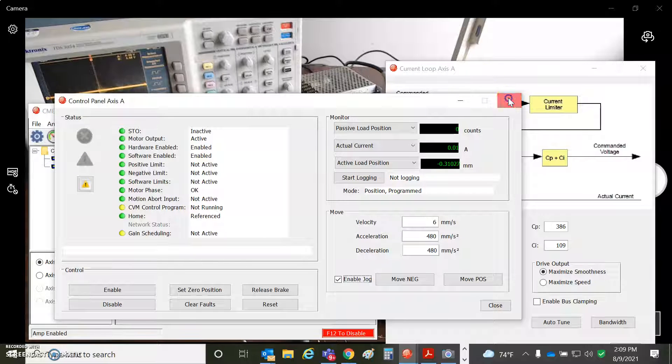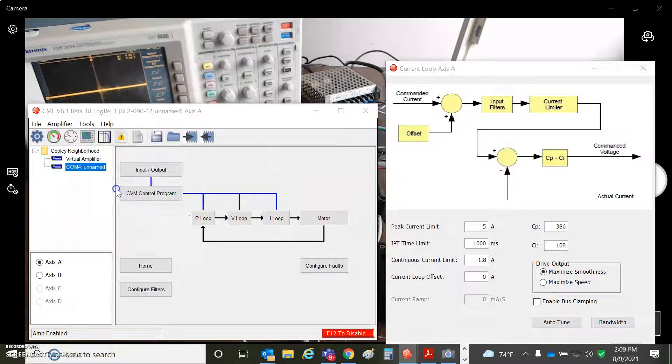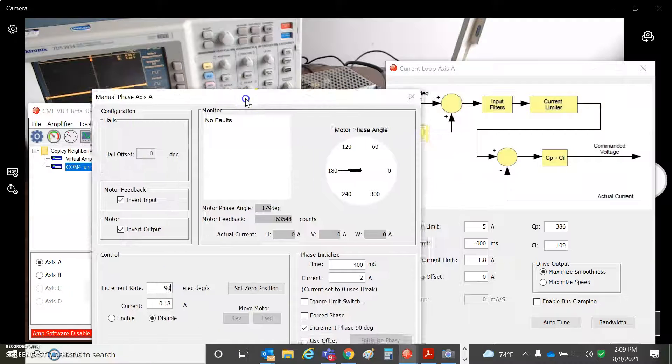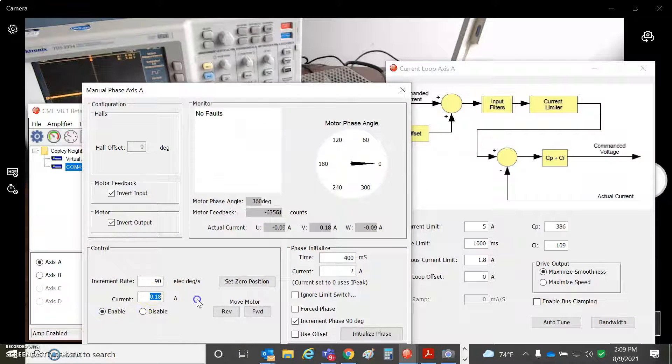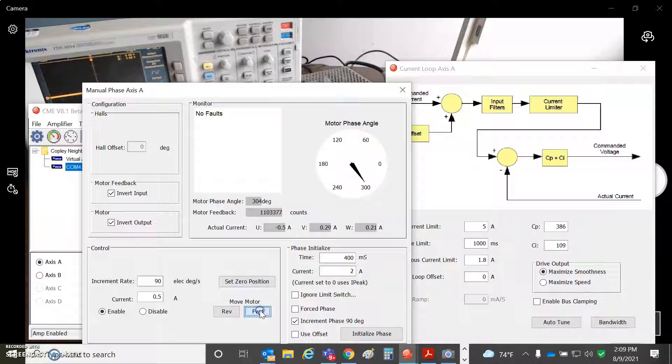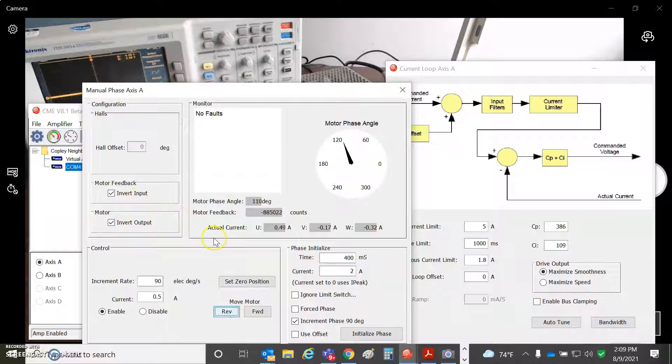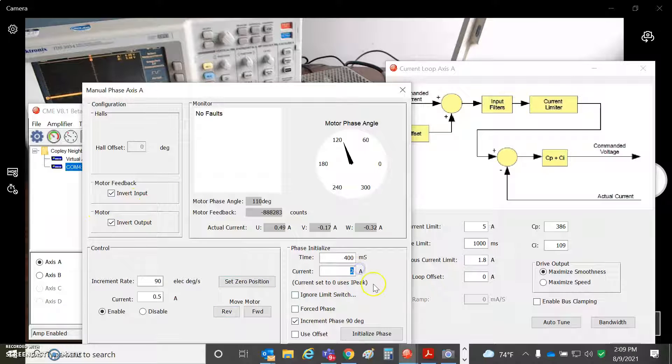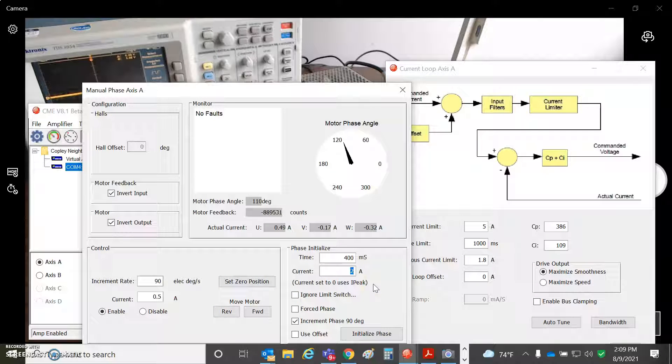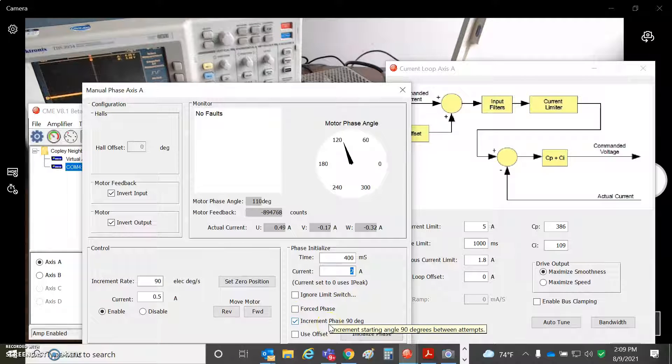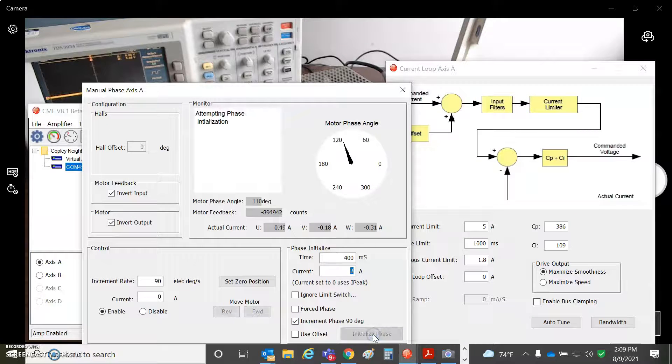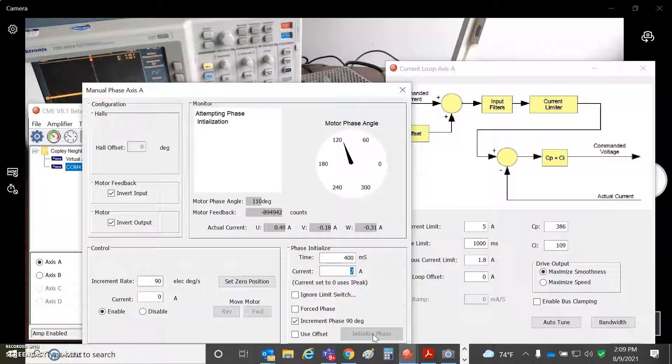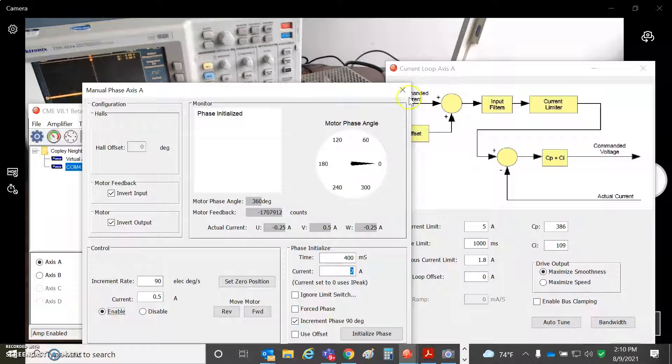Give it a moment to do the little wiggle algorithm. This option to pick for phasing, you can check your when I go forward, give it a little bit more than the smallest amount of 10% current. But when you go forward, counts need to go more positive. And when you go reverse, counts go down. You can invert the motor, invert the feedback to get it to agree. And I set the phase ramp to 2 amps instead of 4 amps for peak. I'm using a little more than continuous, but it's fine. And I said, don't give up. Maybe hit the hard stop and you want to try applying phase current in the other direction. It'll go the other way. So you can test the phase in it here under all these crazy conditions, make sure it works. But at the end, after the phasing is done, it's phased.